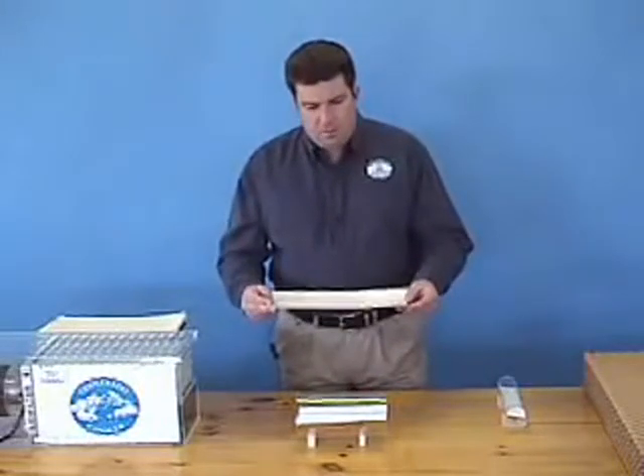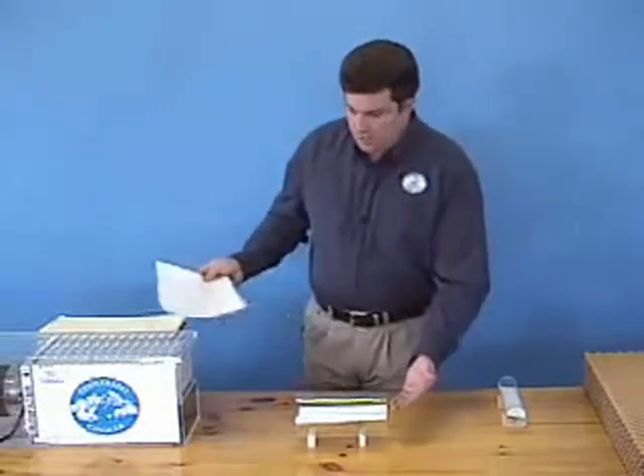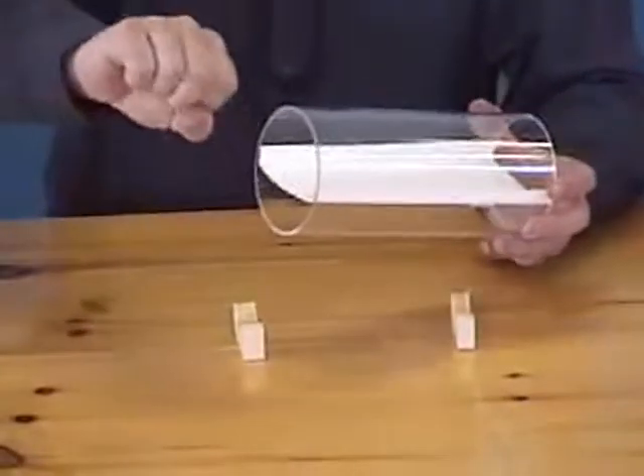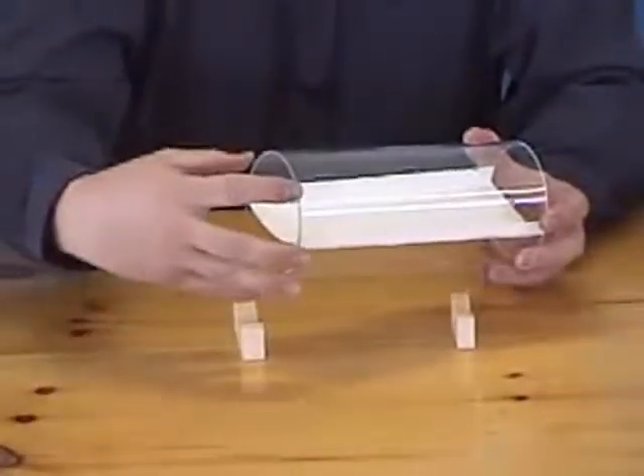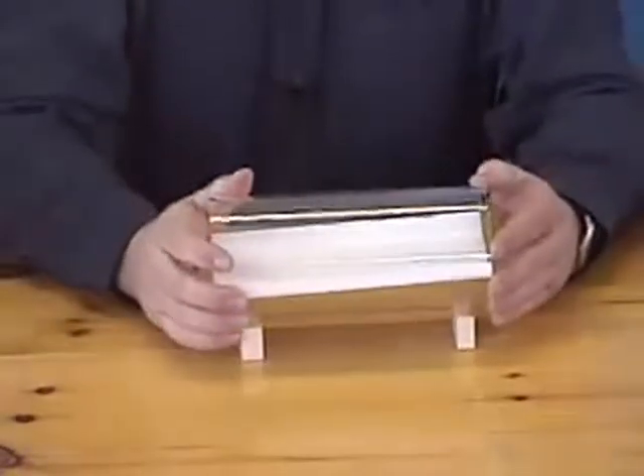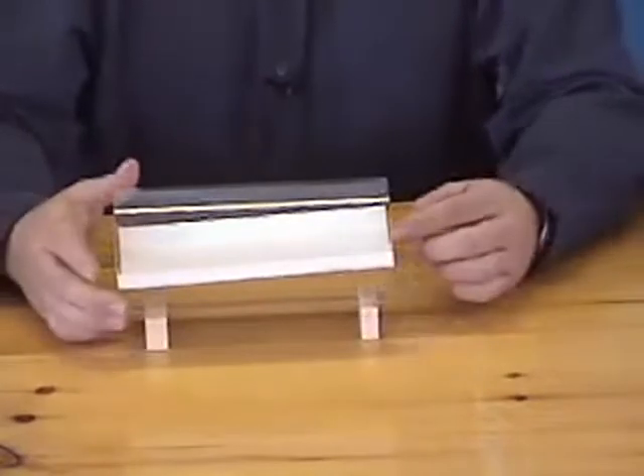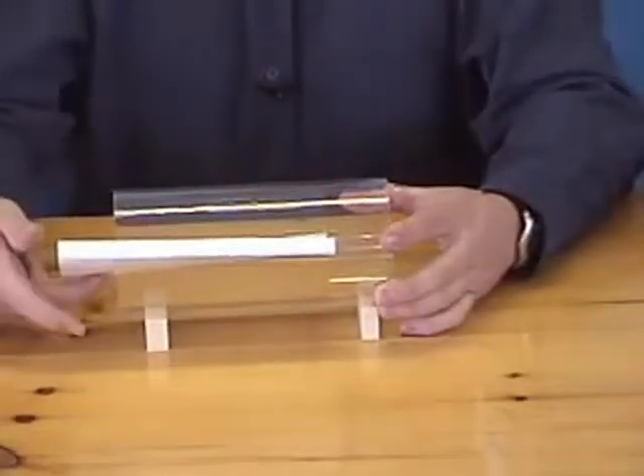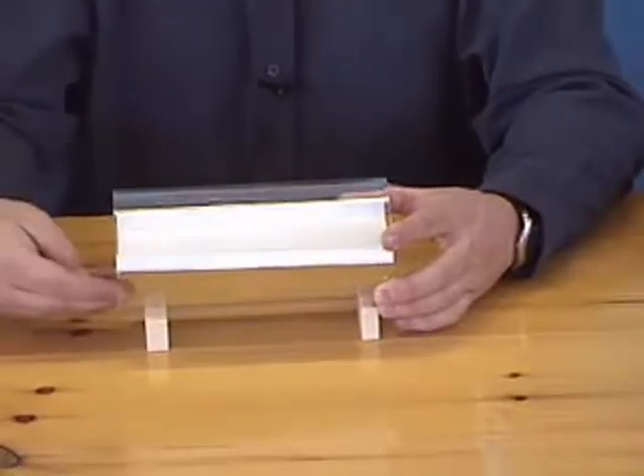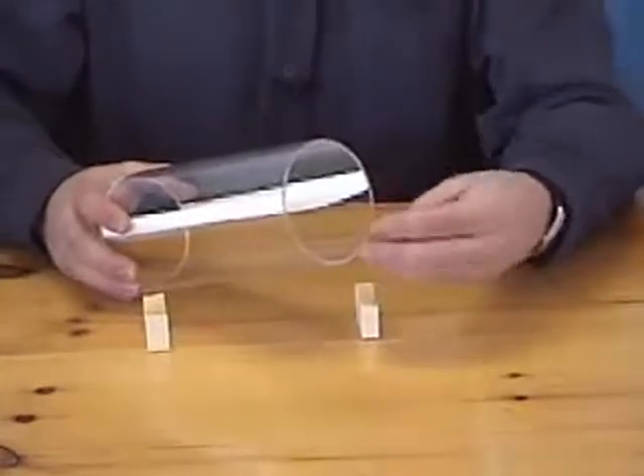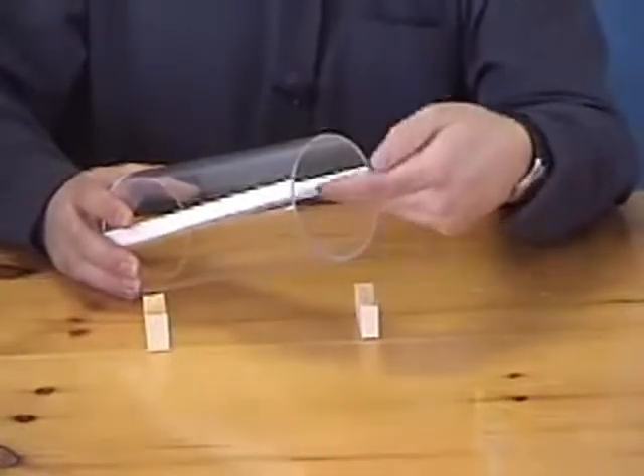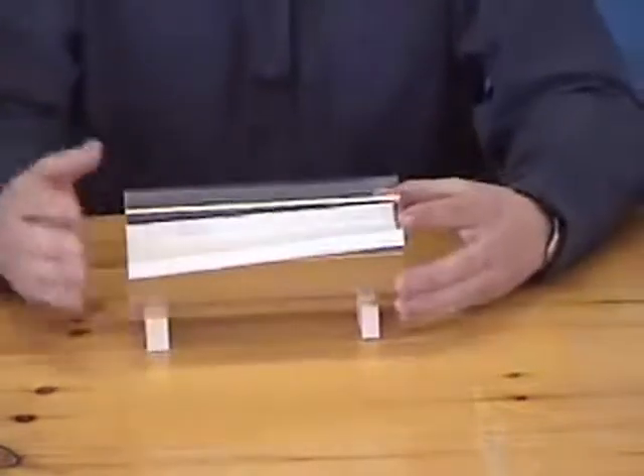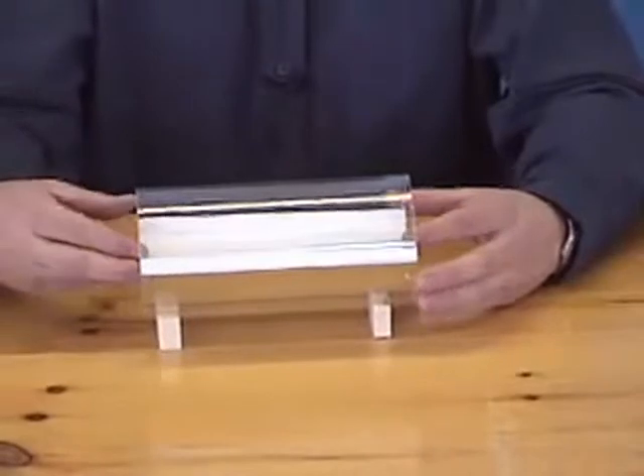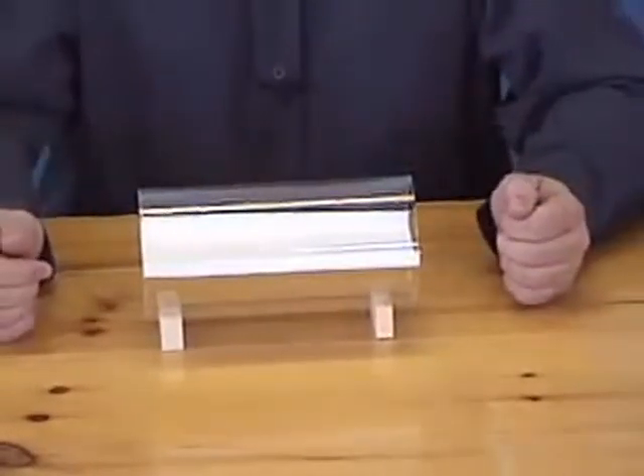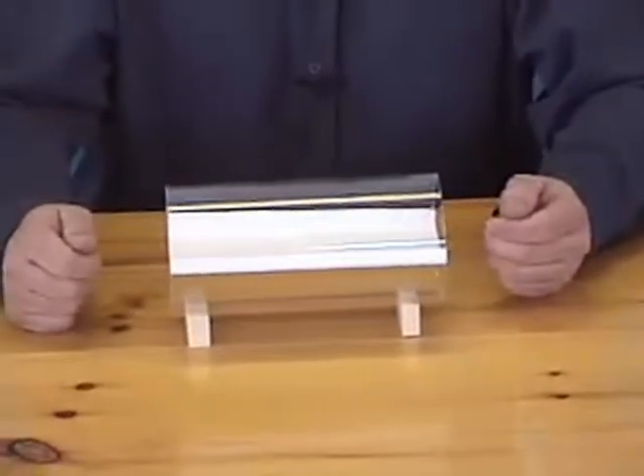Now imagine mounting this plastic-coated paper in the middle of a long insulated tube, much longer than you have here. Then imagine wetting the paper side with water and blowing air through the tube. The air on the wet side is going to absorb moisture until it reaches the wet bulb temperature. That process will pull heat away from the plastic, which will in turn pull heat away from the adjacent airstream. When you come out the other end of this long imaginary tube, the air on the plastic side will be dry, and it will be close to the wet bulb temperature of the entering airstream. This is indirect evaporative cooling. It is both a heat and a mass exchange process.